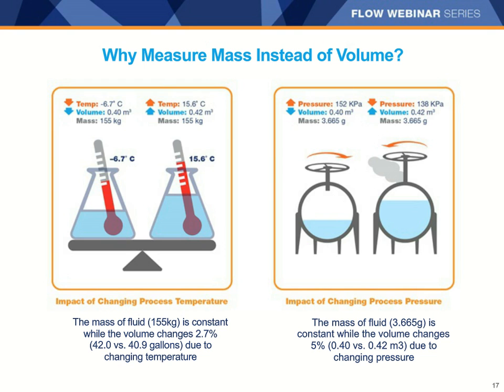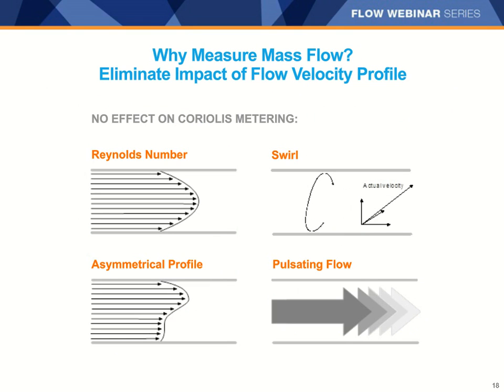The same principle applies with pressure, mainly when talking about gas. As pressure changes, so does the density and the volume, but mass always stays the same. Because Coriolis meters measure mass directly, they're not affected by changing Reynolds numbers, flow profiles, or by turbulent, swirling, or pulsating flows. They require no straight runs of pipe, and because of this, their installations tend to be simpler and less expensive than traditional flow technologies that require straight runs of pipe, pressure and temperature compensation, and in some cases, flow straighteners.